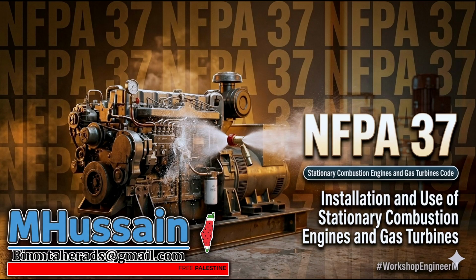For indoor rooms, the baseline is passive protection, a 1-hour fire-rated vault. Or a 2-hour vault for mission-critical facilities, like data centers or hospitals. But walls just hold the fire in. We have to actually put it out. Which brings us to the suppression showdown. Clean agents versus sprinklers. Data centers and hospitals absolutely dread water damage. Right, because if a standard sprinkler head pops over a 2-megawatt generator, it's dumping gallons of water onto high-voltage electronics. The water shorts out the alternator, ruins the digital controls, and if the engine breathes it in, it hydrolocks the cylinders. The fire is out, but the multi-million-dollar machine is garbage.